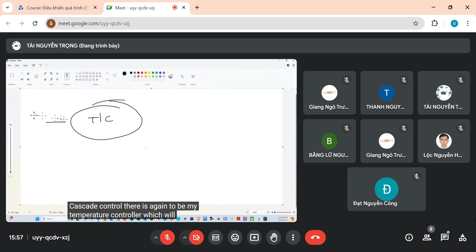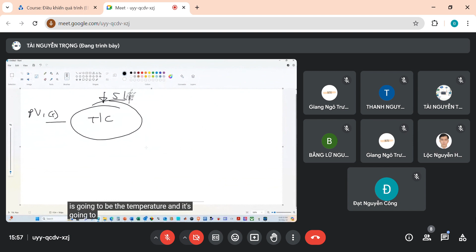In the case of a cascade control, there is going to be my temperature controller, which will have its own process variable coming in, which is going to be the temperature, and it's going to have a set point. The output of that controller is going to be connected up to the set point of this controller, which is going to be my flow controller. My flow controller is going to have its own process variable coming in, which in this case is going to be the flow, and this controller's output is going to go to my final control element. That, folks, is known as a cascade control.